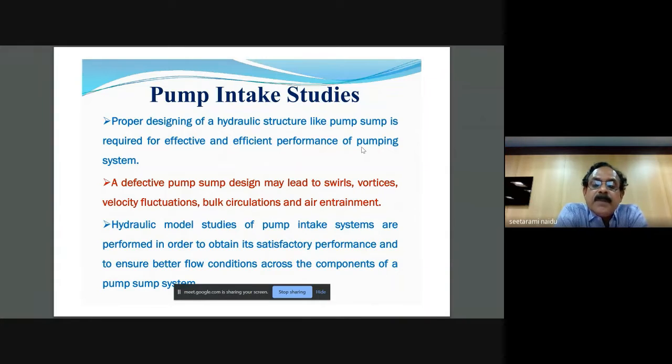So here in pumps, what is most effective in pump performance is the sump levels, the sump design. Sump design is very, very important, with all its parameters, for a healthy performance of a pump. It appears sump is half of a pump performance. It is something like the best brand of a shirt is not useful if it is not fitting the right person. So that measurement, how it fits best into a sump, is very important.